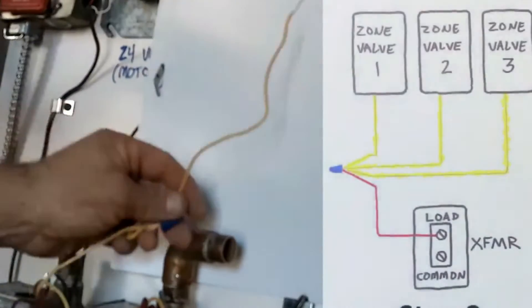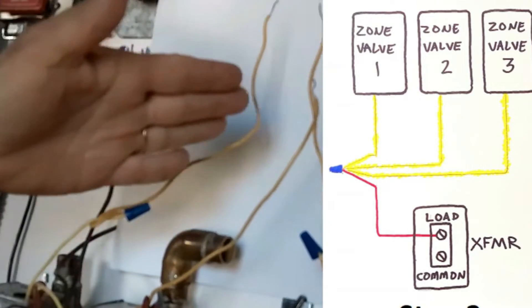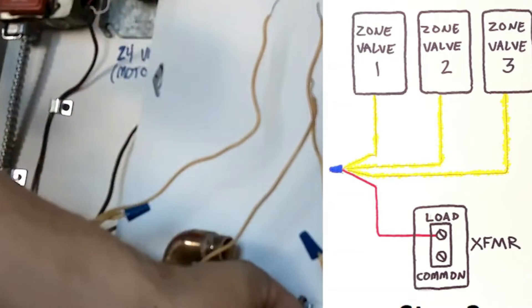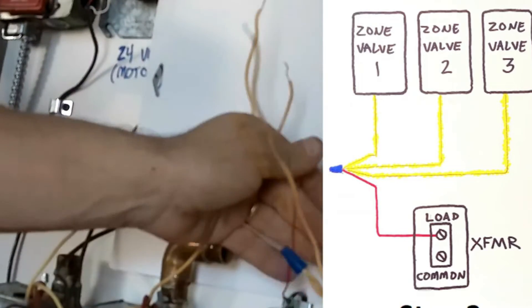Step three, you just take one yellow wire from each zone valve and you will wire all those together with the load wire coming off your external transformer.